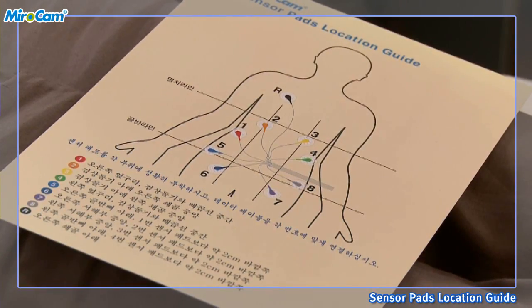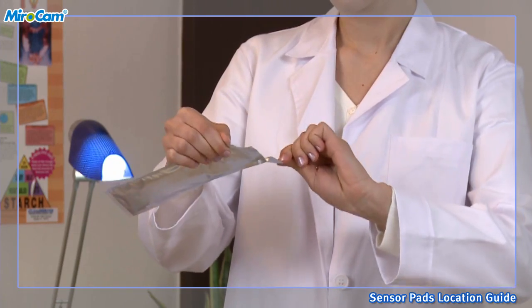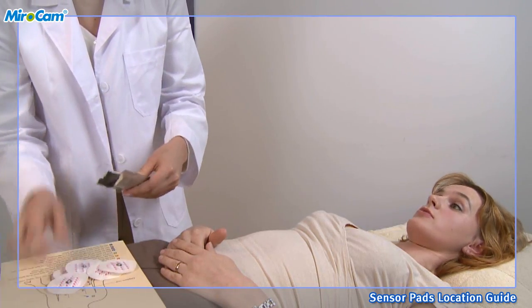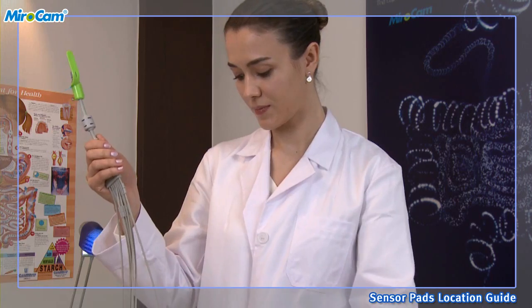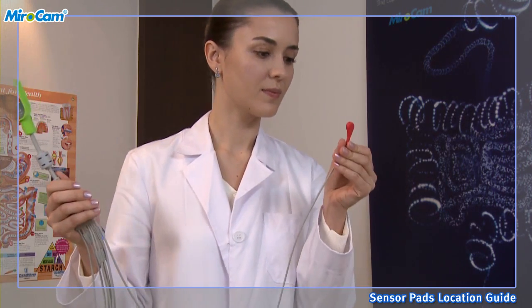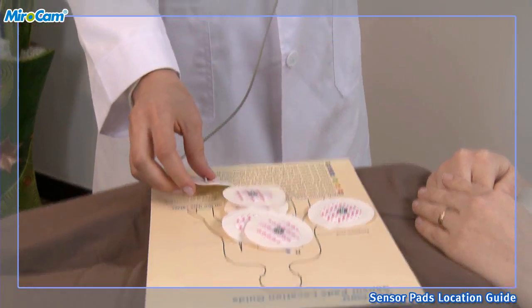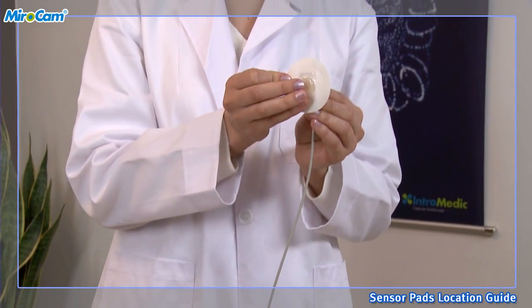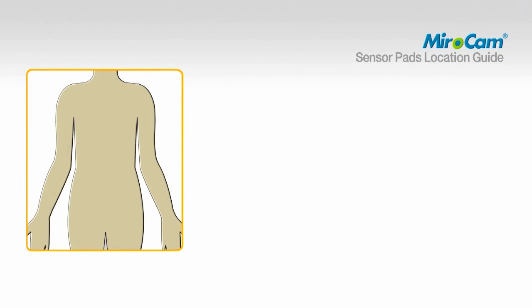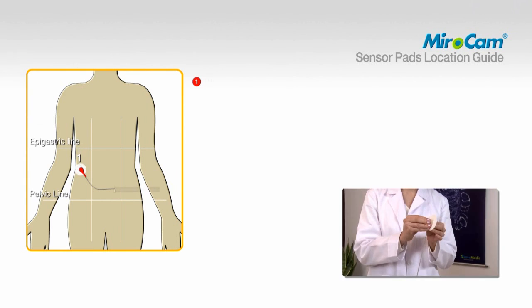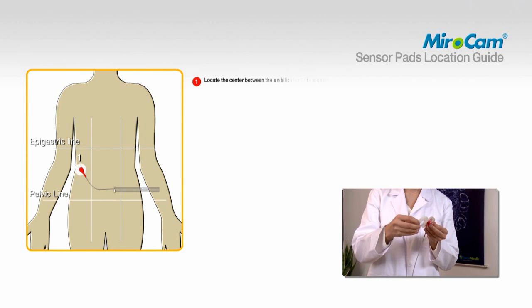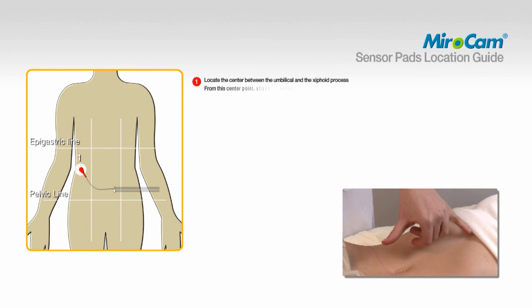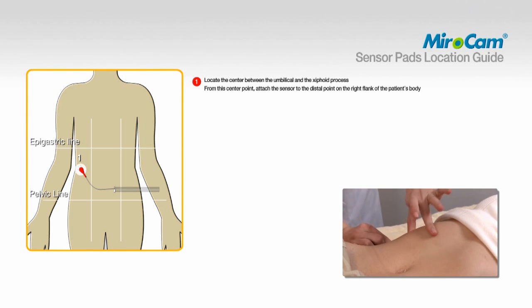Describe where the sensor pads will be attached on the patient. Open the bag of sensor pads and attach them to the data cables prior to affixing to the patient. Attach sensor pads according to the color and number on the data cables as follows. To attach pad number 1, locate the center between the umbilical and the xiphoid process. From this center point, attach sensor to the distal point on the right flank of the patient's body.